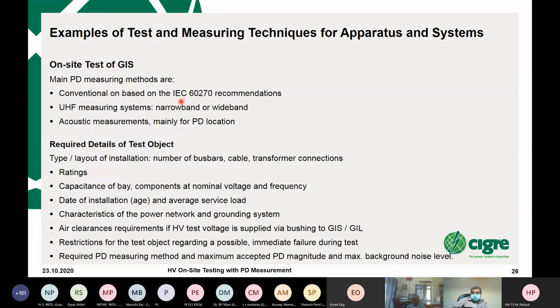I have done it with all of these things personally on a GIS, so with a coupling capacitor according to this conventional method. And then the other is the UHF technology, ultra high frequency. It means you go up to 1 gigahertz or even higher, narrowband or wideband. The other one is acoustic. It's very precise. Precise means half a meter or even better, but this is very time consuming. And the best way is to do everything. And this can be done, and should be, if it's a very important substation. On the next slide you see how these can be the best combination.